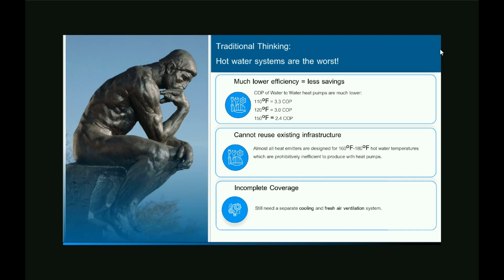There's a traditional thinking out there right now that hot water systems are the worst to retrofit. And it kind of makes sense if you look at it for 3 main reasons. Number one, the efficiency of a hot water system is typically quite a bit lower than a comparable ground source forced air heat pump. So if you're trying to replicate the high temperatures of a hot water boiler at 180 degrees, frankly, the efficiency is going to be prohibitively inefficient, right? And so the max that you typically want to use is about 120 degrees to remain efficient and have a system that can get a reasonable COP. But even then, that's a COP of about a 3.